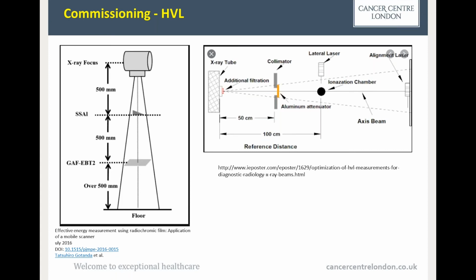This measurement required specific setups, and the most important was that we had to simulate a small field to represent the primary beam as much as possible while reducing scatter. Also, the distance between attenuator and source should be at least 50 centimeters to avoid any scatter, and the chamber had to be at a specific distance. Unfortunately, because these kV rooms are often relatively small, it is crucial to check that the chamber is far away from walls, floor, and any constructions which can be sources of scatter radiation.